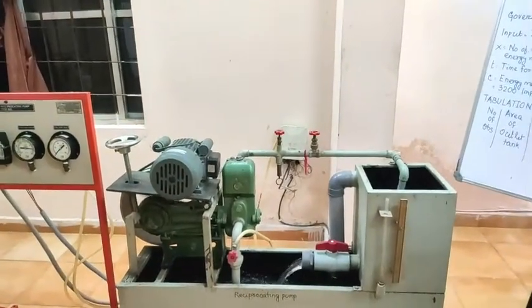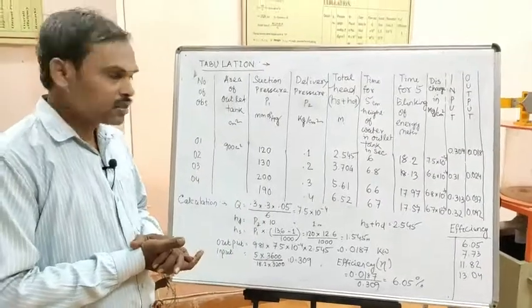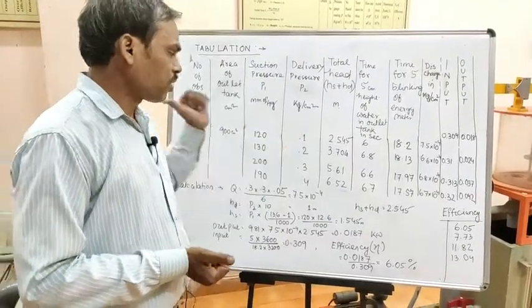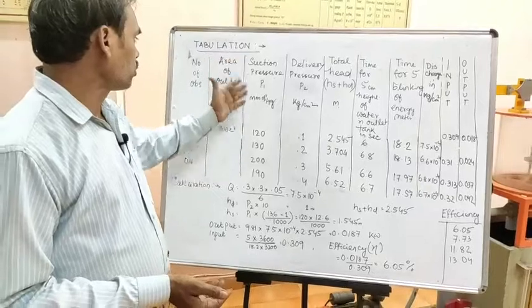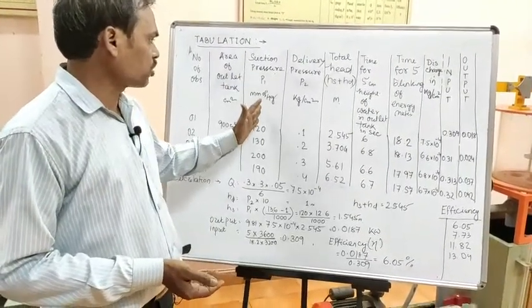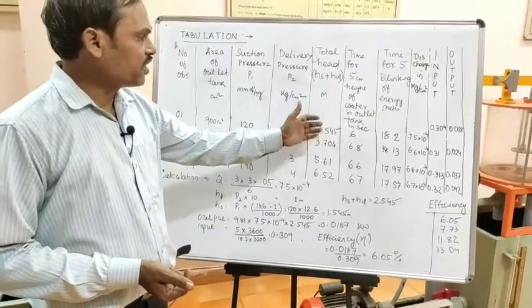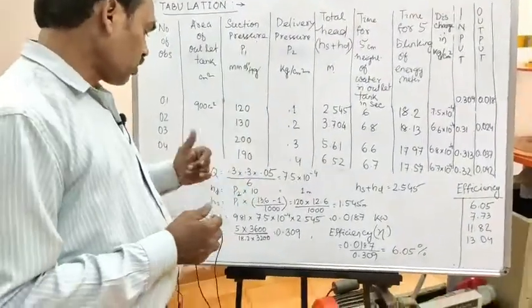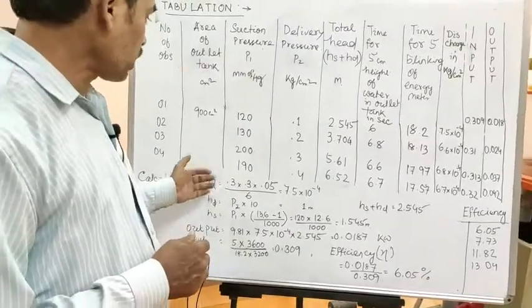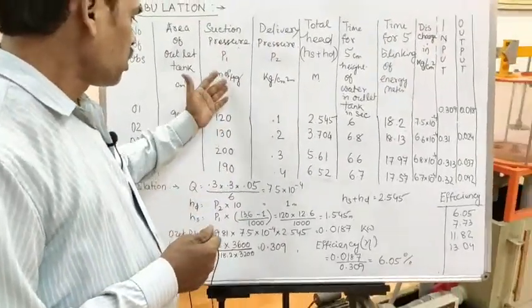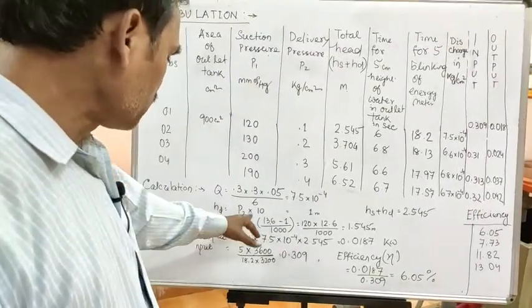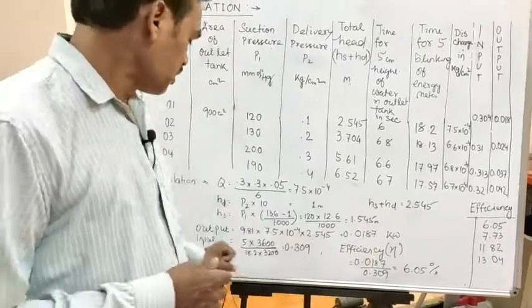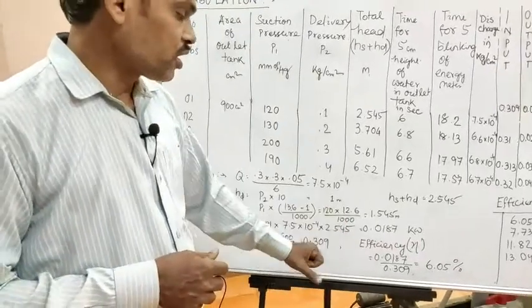Now we go for the tabulation part. After the experiment, the collected data are: area of the outlet tank is 900 cm². We record suction pressure, delivery pressure, total head, time for 5 cm height rise in the outlet tank, and time for 5 blinks of the energy meter. We put these values into the equations to convert suction and delivery pressure into head, then find the input and output power, and hence the efficiency.